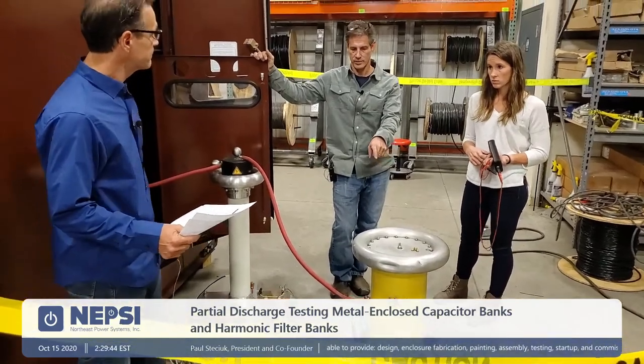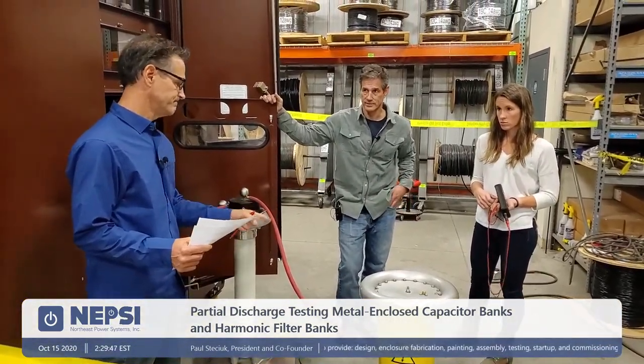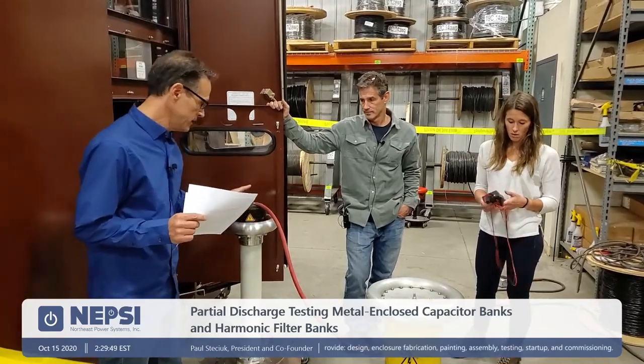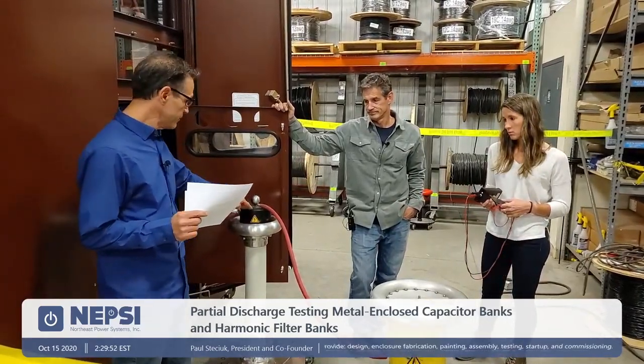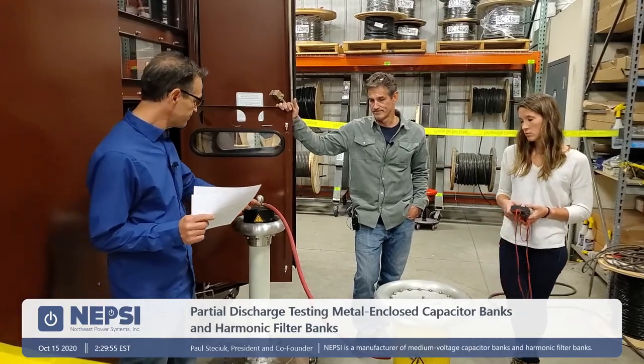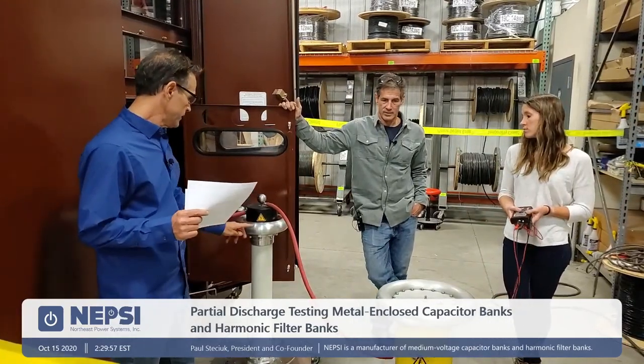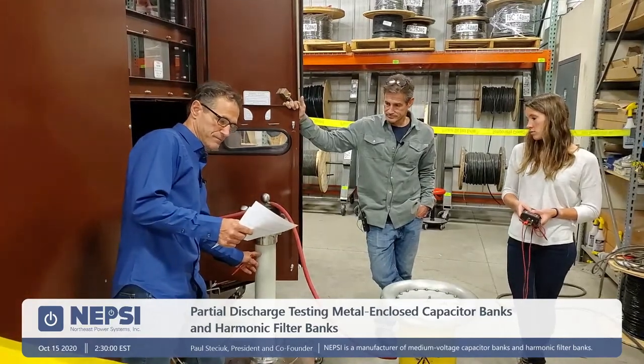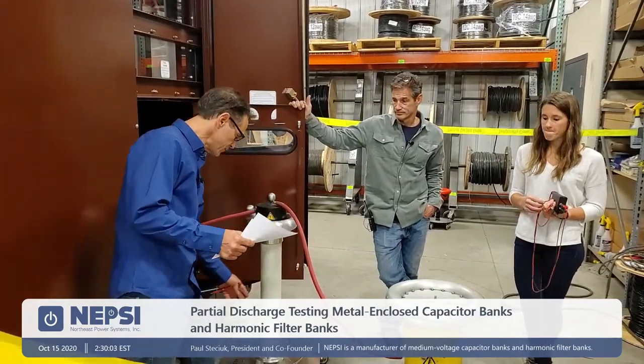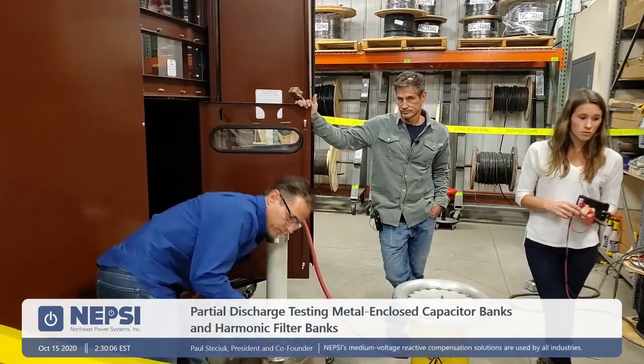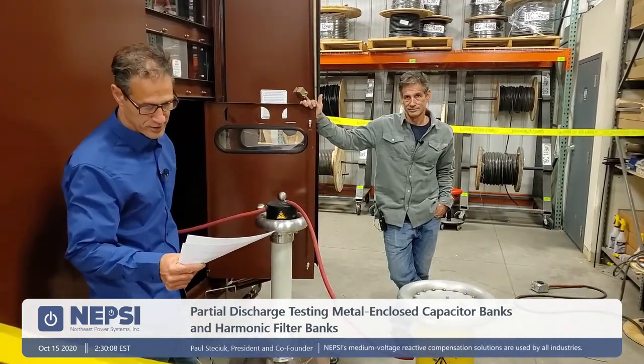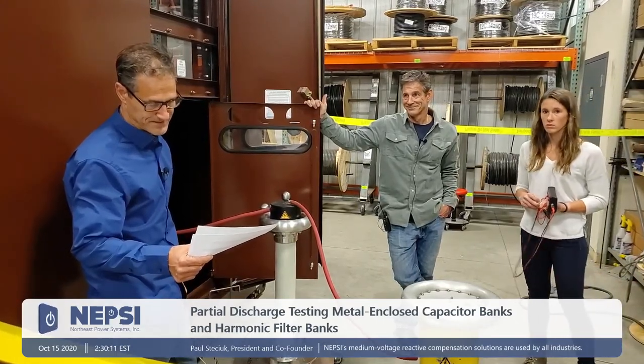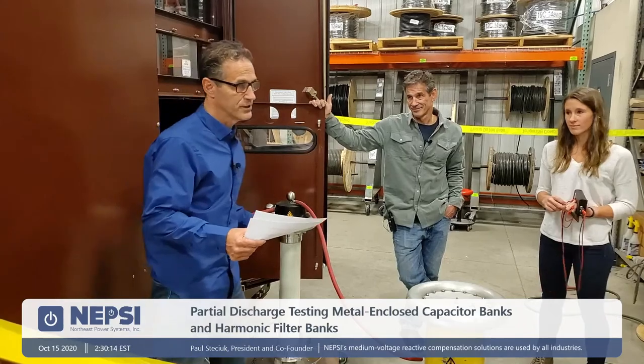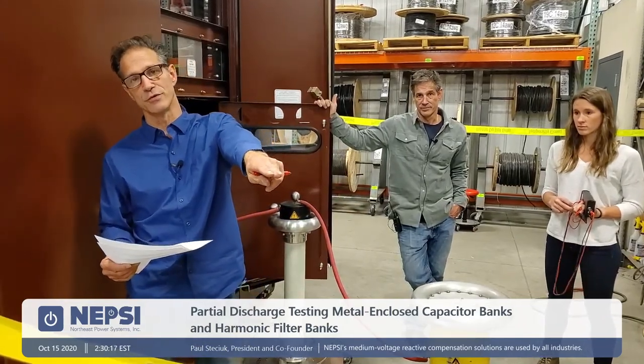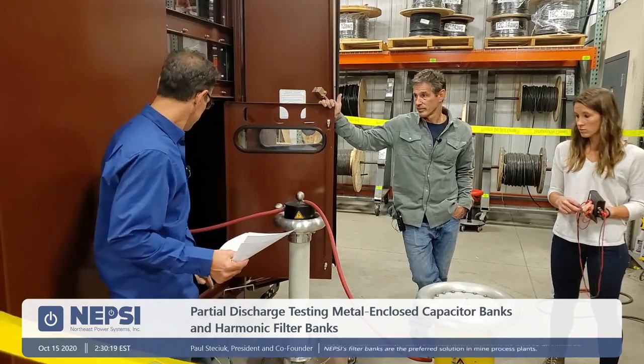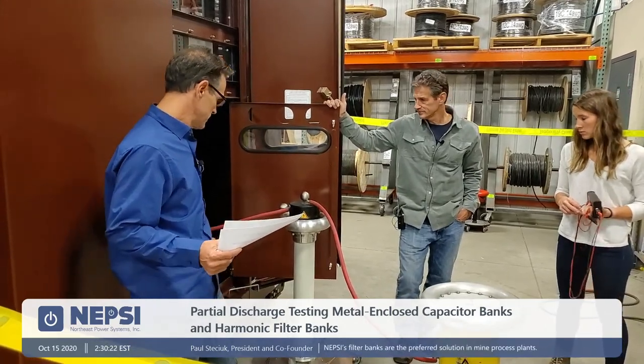And just, I want to add, Paul, that this is an AC high pot test, not a DC high pot test. Right. Good point, AC high pot test. And this is a filter on top here. So we're taking the signal, we're bringing it into the equipment. This is the coupling capacitor, the coupling device, which actually connects it to the measurement instrument over here. Did I miss anything, Pete? No, that's it. Calibrator device.